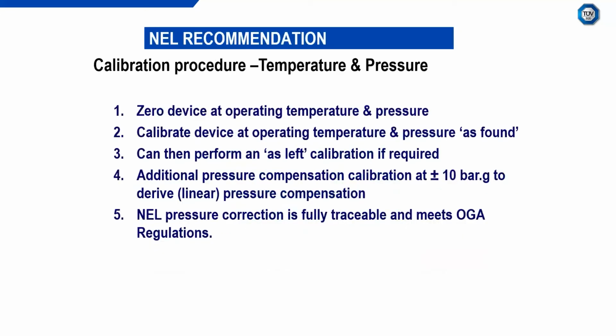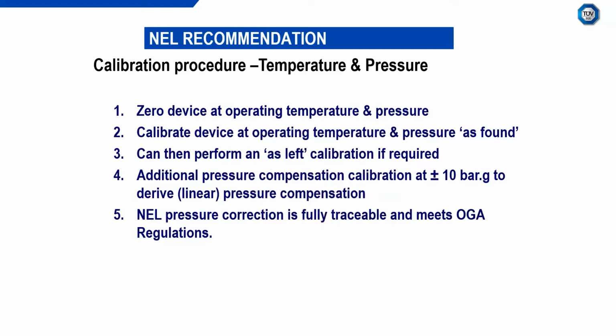So what do NEL recommend? The TUV SUD National Engineering Laboratory, we often shorten it to NEL. We recommend that you try to calibrate as close to service conditions as feasible. It's not always going to be feasible if you're operating at, say, 200 degrees Celsius and 150 bar. There isn't a flow facility in the world that can calibrate devices at that condition, but hopefully you can try and get close to it. And the good thing about the pressure effect is you can work out what it is by operating at a couple of pressures and seeing how linear it is, getting your linear pressure correction. And from the research we've completed, you can extrapolate the pressure effect to certain conditions. Maybe we wouldn't be overly confident extrapolating it to magnitudes higher pressures. But if you're extrapolating maybe to an extra 10, 15, 20 bar, it should be sufficient.